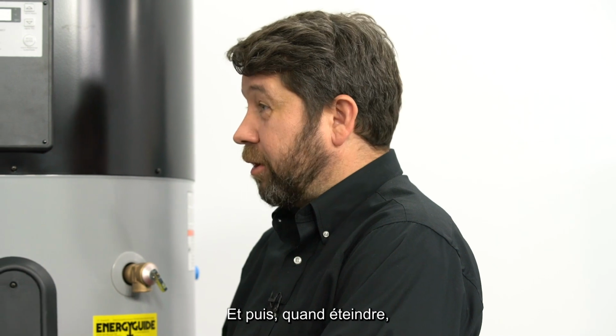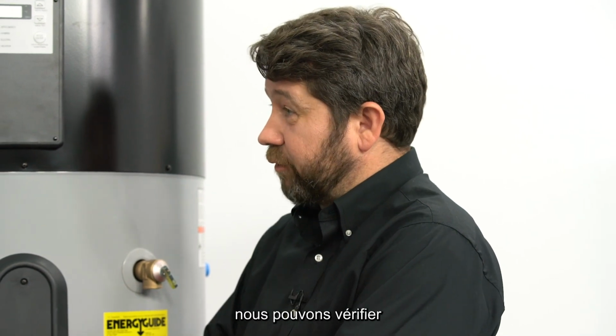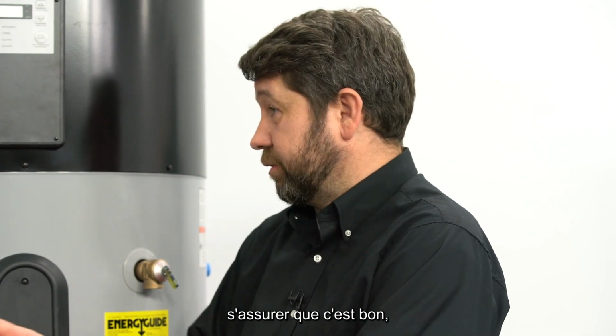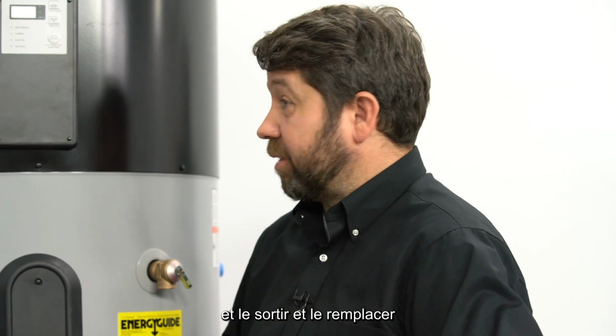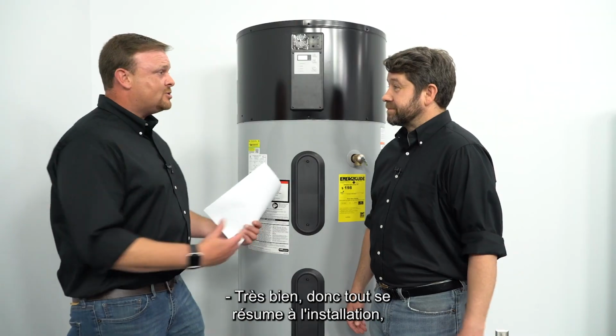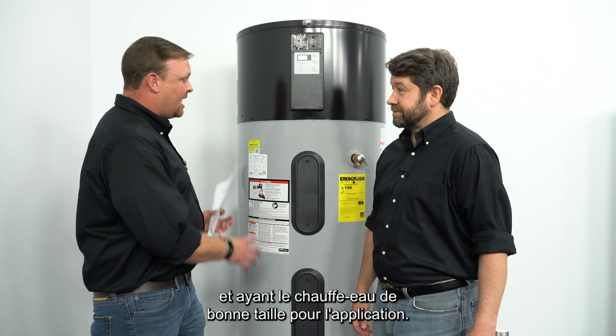And then with the power off, just like we would with standard electric, we can check for continuity or for ohms through that element, make sure that it's good, and pull it out and replace it just like you would a standard electric heater.